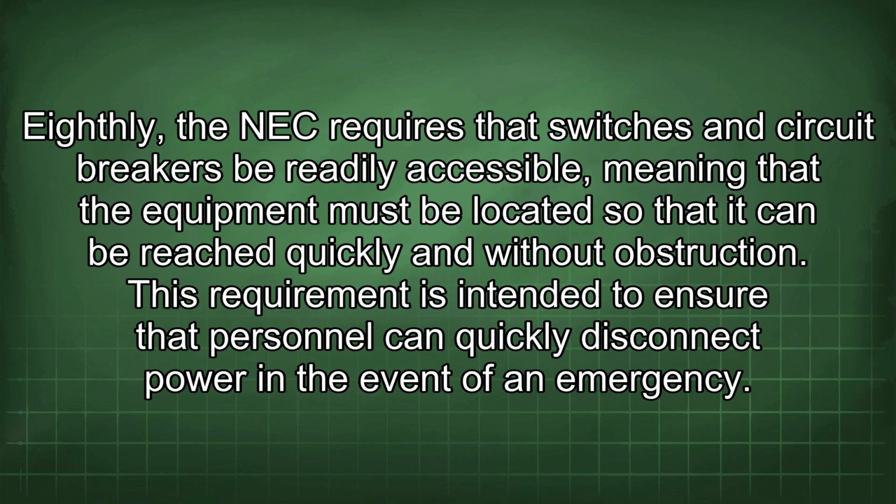Eighthly, the NEC requires that switches and circuit breakers be readily accessible, meaning that the equipment must be located so that it can be reached quickly and without obstruction. This requirement is intended to ensure that personnel can quickly disconnect power in the event of an emergency.